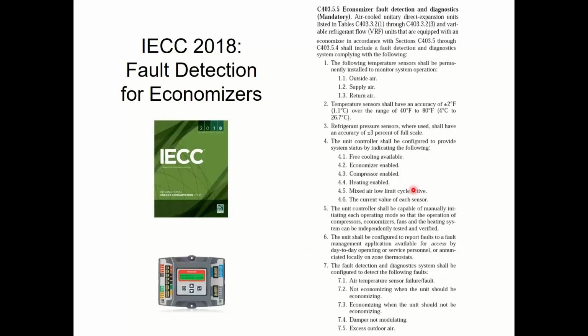If you've got a building automation system instead, that's fine. Make sure they do all those different things. The interesting thing from the field standpoint is item number 6. That's the only one I want to read to you. The unit shall be configured to report faults to a fault management application available for access by day-to-day operating or service personnel. What's a fault management application? That's a building automation system. Somewhere it's got to notify the building manager that there's a problem on a day-to-day accessible basis.